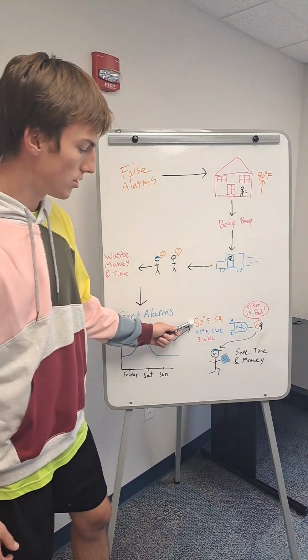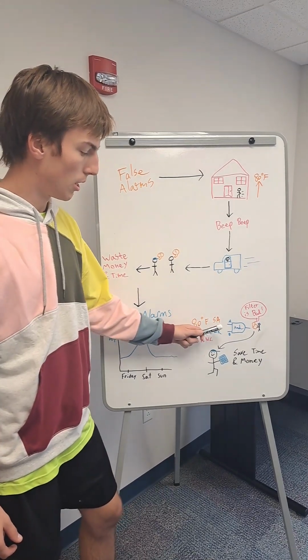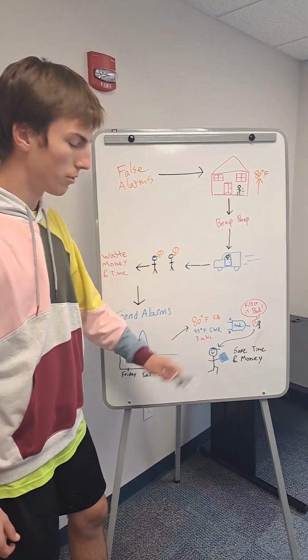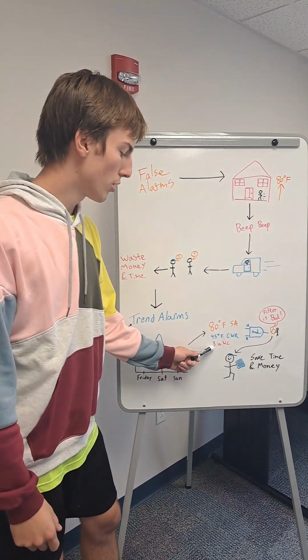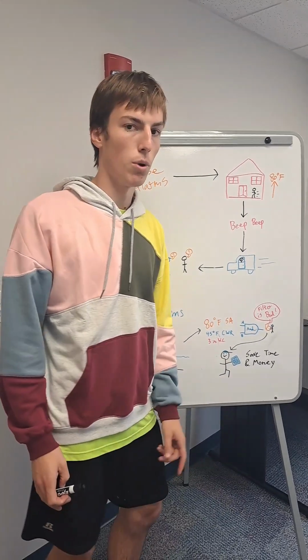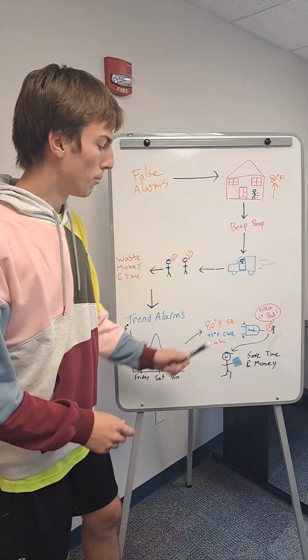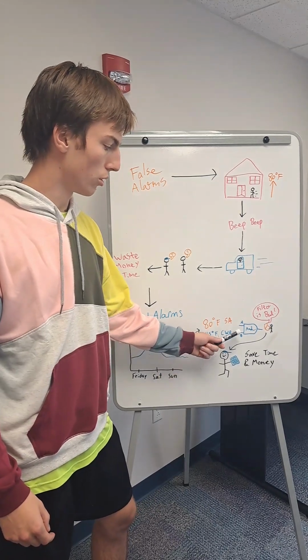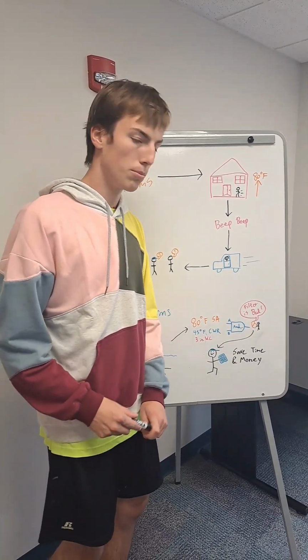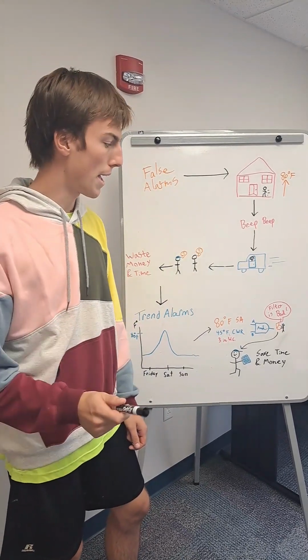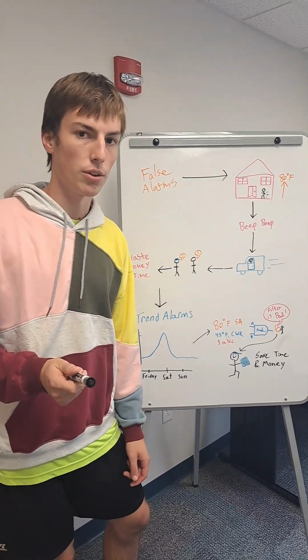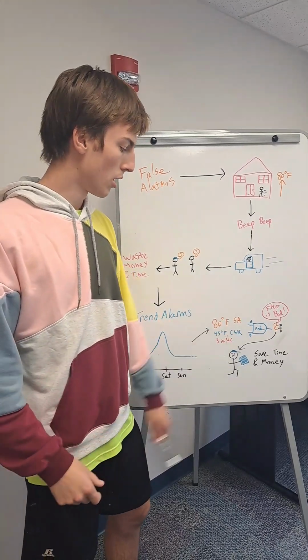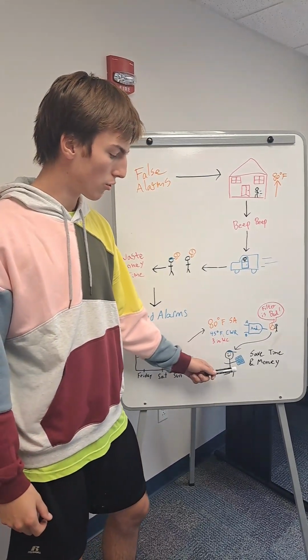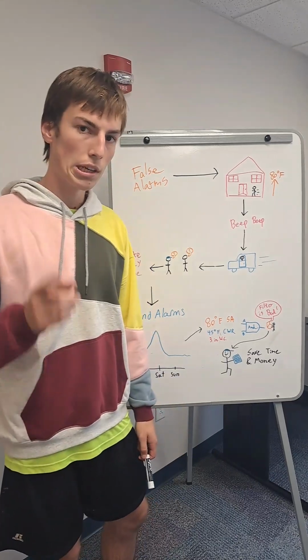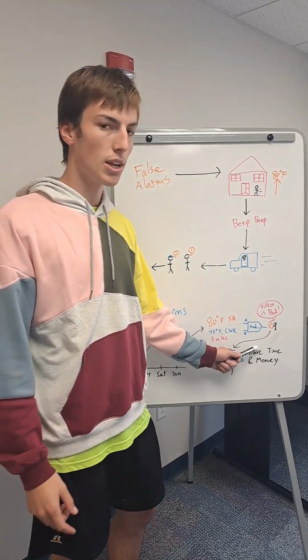It could be 80 degrees in there with the supply air. The chilled water return is 45 degrees, meaning it's not properly heating up, and the pressure drop across the filter is 3 inches of water column. All of those things would be fed into a logic controller, processed and sent to the technician's computer that would say the filter is bad, because they're all working together and our programs are using logic. The technician can then grab the right size filter, walk over there, check it out, replace it if it's bad, and this saves time and money.